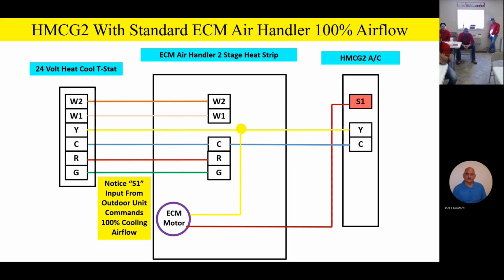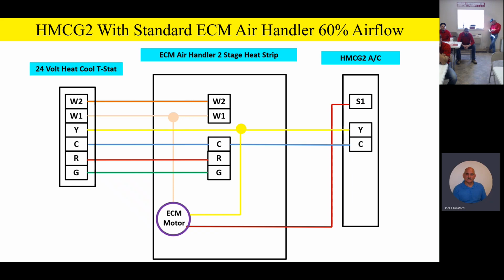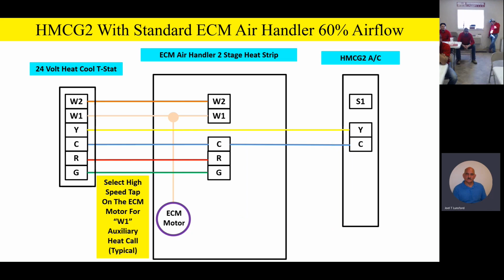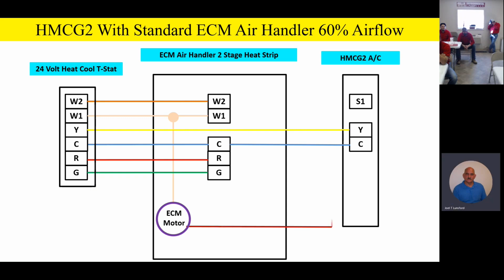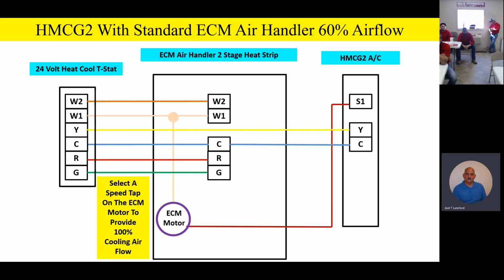Can you go back to the last clip where you had the ECM motor tapped into W1? So what happened from there to the next clip? Sorry, I was writing something down. That's okay. This is in case you have an auxiliary heat call. Let me back up here. You're going to select a speed tap, the high speed tap, for that auxiliary heat. Then for your 100% airflow, you're going to go to S1. So whatever speed tap you're using for 100% airflow, you're going to tie that onto S1. And then off your yellow wire, you're going to tap off of that and go to the motor for your 60 to 65% airflow.